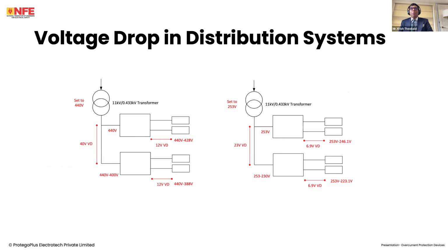Now, the more I present this, the more questions I get about distribution systems. I can already see that there are some questions in the webinar chat. How do we calculate voltage drop in a distribution system? Okay, let's look at an example. Let's say you have an 11 kilovolt, 433 volt transformer. It doesn't really matter what the primary voltage is for the case of volt drop. What do we do? Step number one, we set a tolerance value.